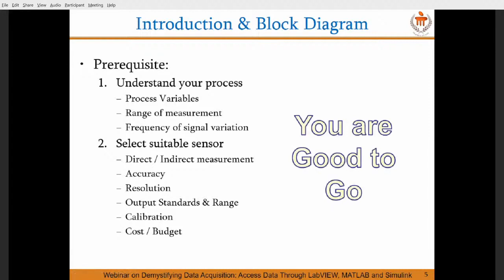Now let us take a simple example. Let's say I'm going to measure temperature for a range of 0 to 1200 degrees centigrade. I am selecting a thermocouple. For 0 degrees centigrade, it's going to give me 0 millivolt. For 1200 degrees centigrade, it is going to give me 48.838 millivolt. So this is the nature of this particular sensor.